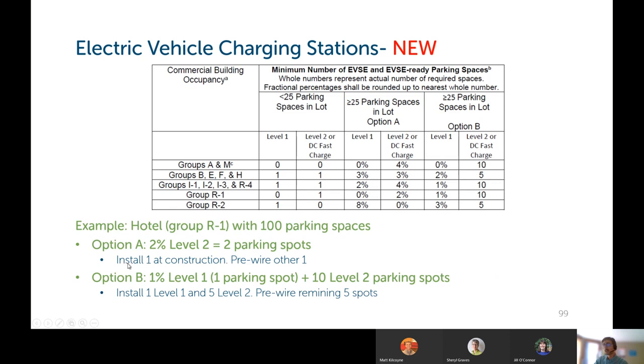The code says you only need to install half of those. So really, you only need to install 1 when you construct the building and pre-wire the other Level 2 charging station. If you follow option B, it says you need 1% of the parking spots to be Level 1, which is 1 Level 1 parking spot, and 10 additional Level 2 parking spots. Again, if you're going to install half of those, you would have to install the 1 Level 1 charging spot and 5 of the Level 2 charging stations, and pre-wire the remaining 5 Level 2 spots for the future. So hopefully that makes a bit more sense.